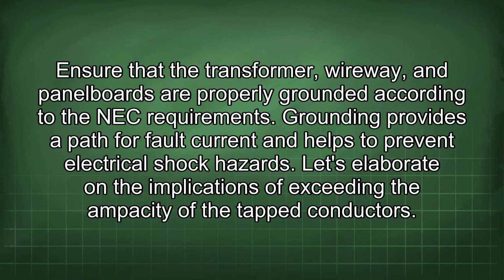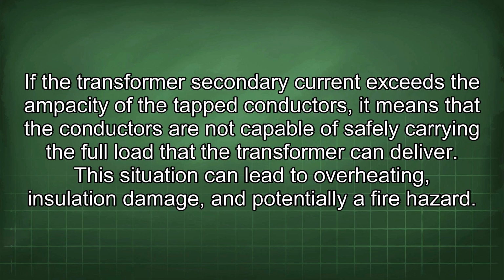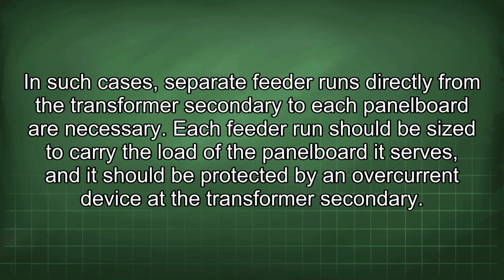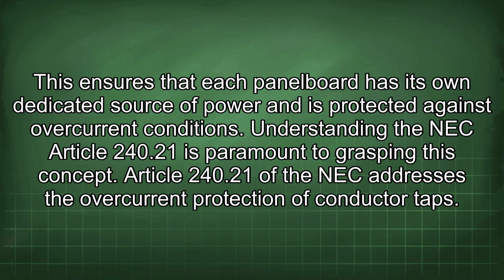Let's elaborate on the implications of exceeding the ampacity of the tapped conductors. If the transformer secondary current exceeds the ampacity of the tapped conductors, it means that the conductors are not capable of safely carrying the full load that the transformer can deliver. This situation can lead to overheating, insulation damage, and potentially a fire hazard. In such cases, separate feeder runs directly from the transformer secondary to each panel board are necessary. Each feeder run should be sized to carry the load of the panel board it serves, and it should be protected by an overcurrent device at the transformer secondary. This ensures that each panel board has its own dedicated source of power and is protected against overcurrent conditions. Understanding NEC Article 240.21 is paramount to grasping this concept.